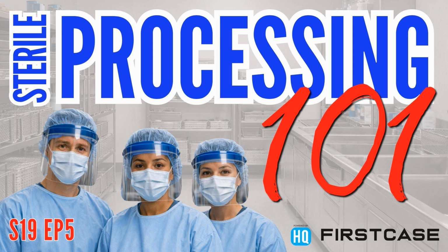So then you pull it out of the sterilizer. Now you have dry but really hot instruments. And so you can't do something with it right away, because if you take something really hot and set it on a cold back table in the OR, it's going to condense, and that water, again, is going to become a risk for contamination. And so we have to let it cool all the way down to room temperature before we can handle it. So that process can take anywhere up to 2 hours or so, depending on the type of instrument.